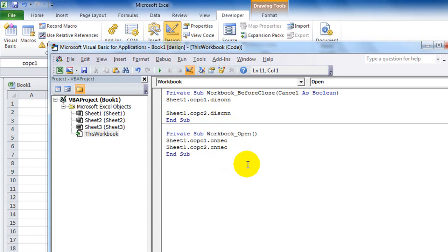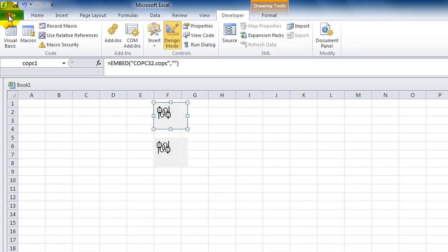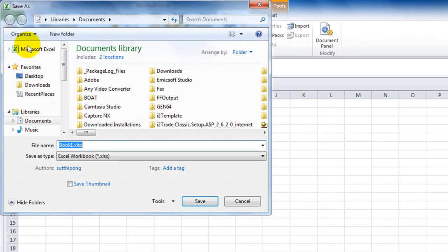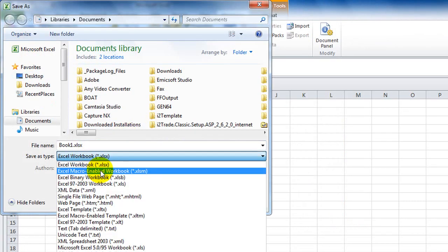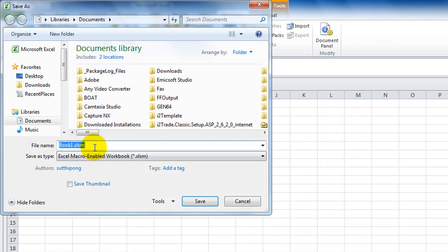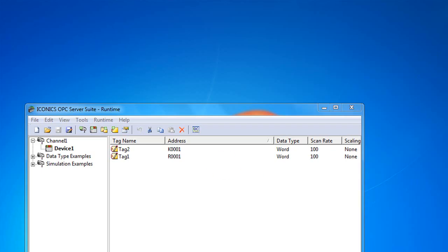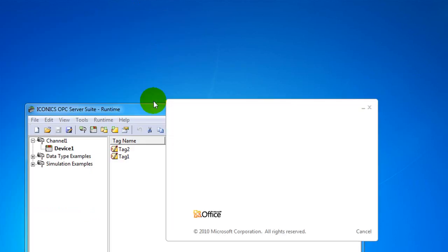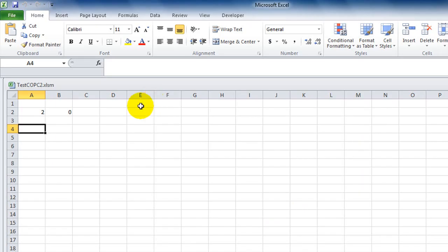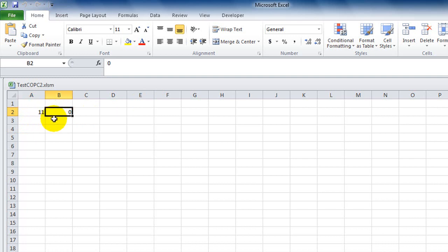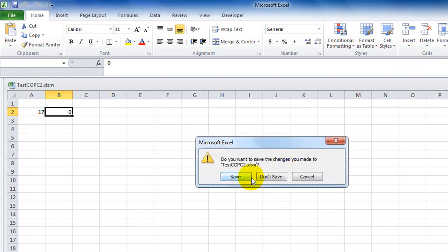Now save the file. Choose File, Save As, and save it as an Excel Macro-Enabled Workbook. Name it TestCOPC2. Now close the workbook and reopen it — Excel will connect to the OPC server automatically and bring the OPC tag values into the sheet. When you close the workbook, it will disconnect from the OPC server.